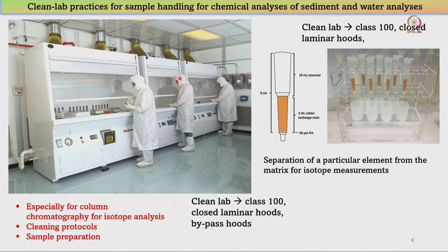Here you will see that there will generally be two kinds. In one particular kind, the clean air will flow through the filter. There will be filters set up all here, and the air will flow out like this. From these vents, these hoods, there will be openings here, and through the filter much cleaner air, which will be pressurized, comes out through the openings. These are called the laminar hoods.